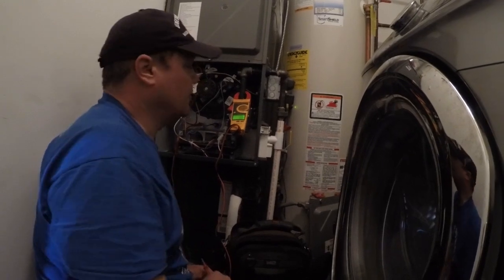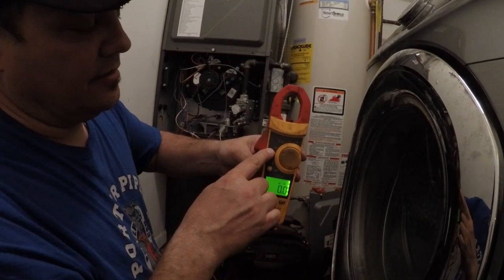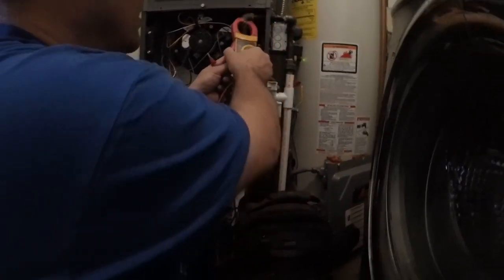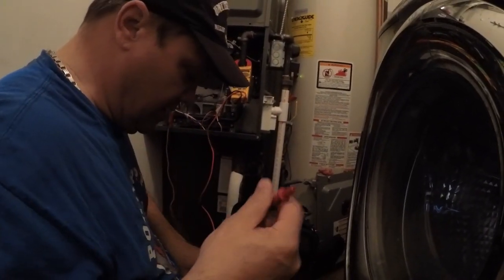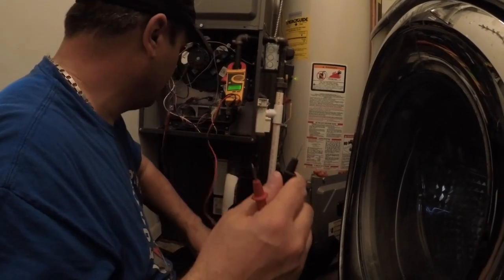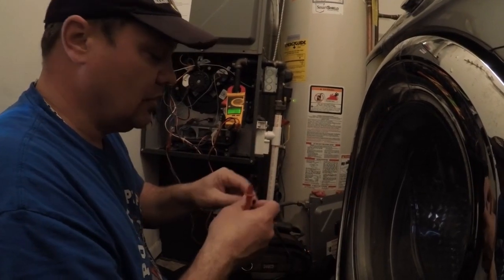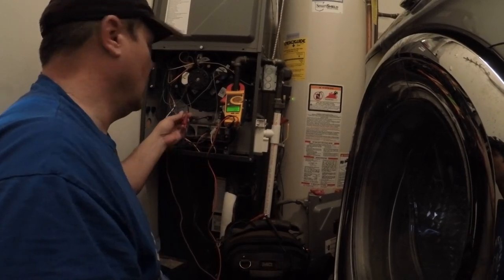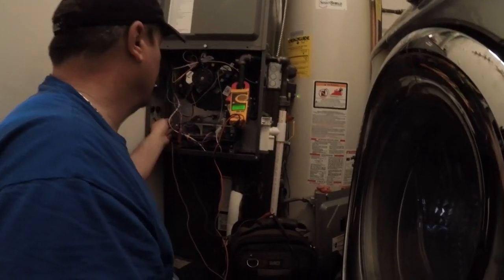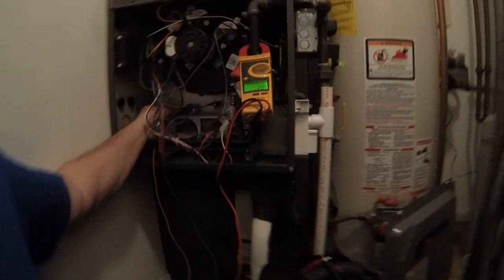I want to test my flame signal. What I use is my Fluke meter set on microamps. I've taken two jumpers — if you didn't have two jumpers like the average service guy, I've got one — and I want to connect one to one lead and one to the next lead.